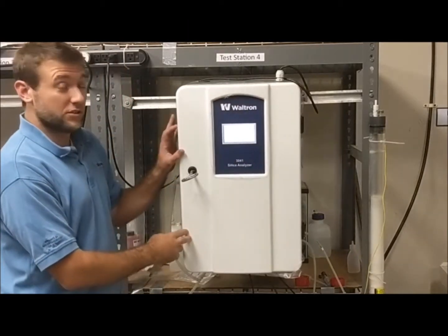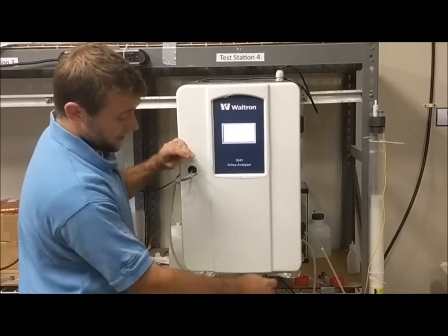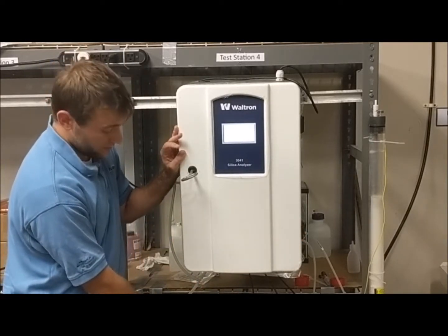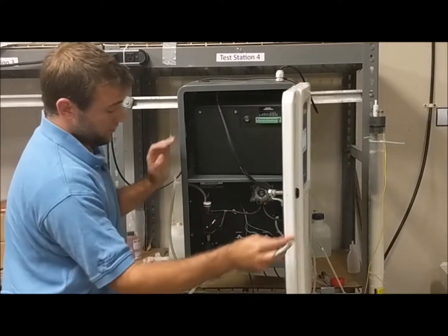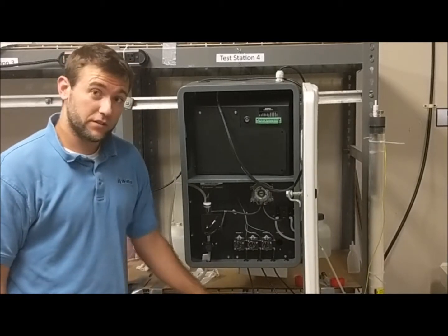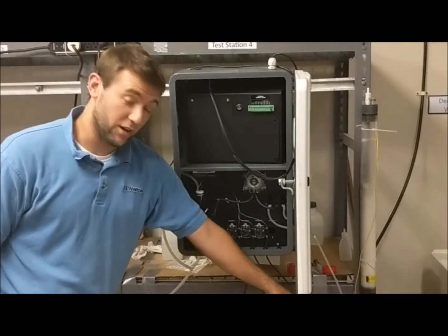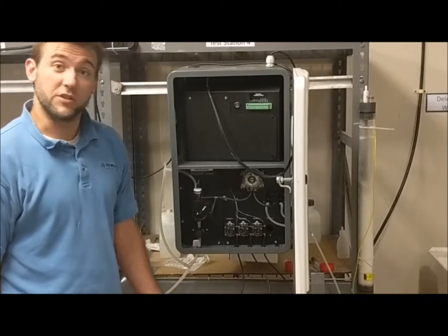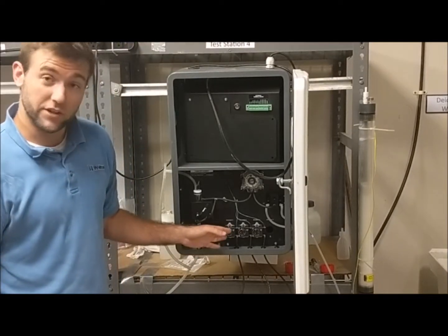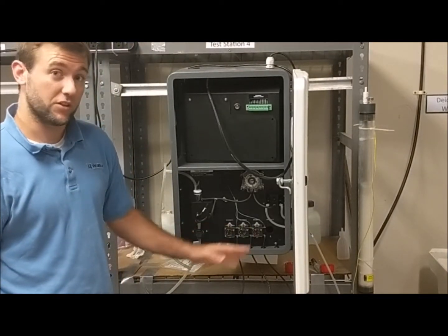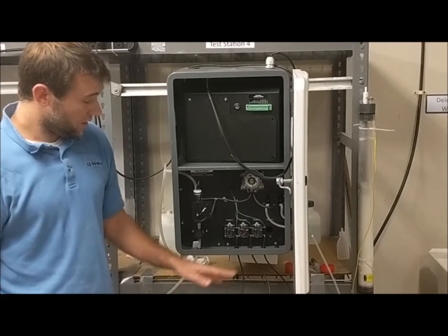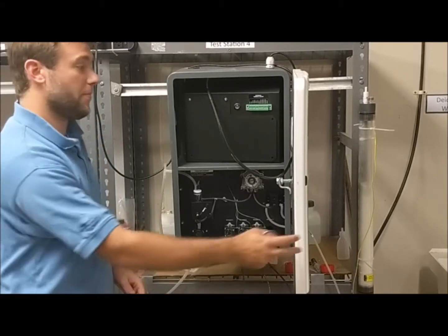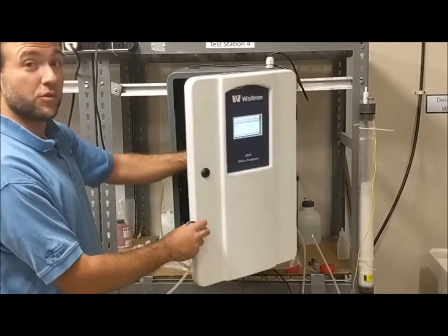As far as wet sections, your sample comes into the side and your reagent should be below the analyzer. You'll need to install your reagent tubing, R1, R2, R3, and your calibration standard. The tubing should be labeled and it should correspond with the reagent pumps that are inside here in your wet section. Once you have all your reagents connected, you need to do a reagent prime before starting the analyzer into operation.